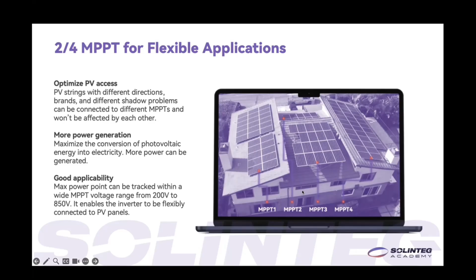For example, over here there is some shadow from this orientation, but for the others there is no such shadow. So if we are using the multiple MPPT choice, the shadow over here won't affect the other PV strings connected to other MPPTs. In this case, we can help to optimize the PV yield, and with multiple MPPTs we can offer our users more power generation. And thanks to the wide MPPT voltage range that our inverter offers, the maximum power point can be tracked, so the inverter can flexibly connect with the PV panels.